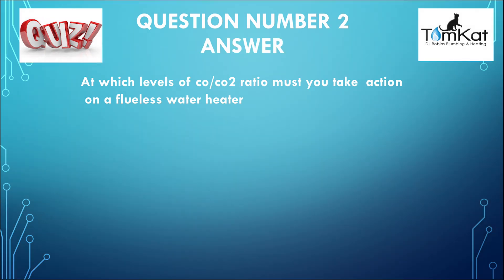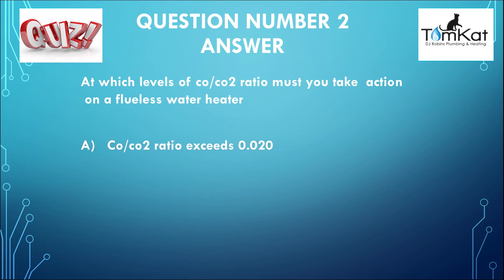Now the answer for question number two: at what levels of CO/CO2 ratio must you take action on a flueless water heater? The answer is A — when the CO/CO2 ratio exceeds 0.020. That's the answer for question number two.